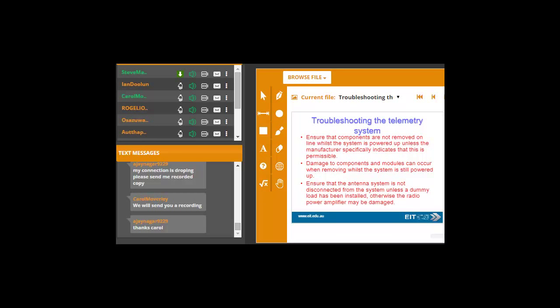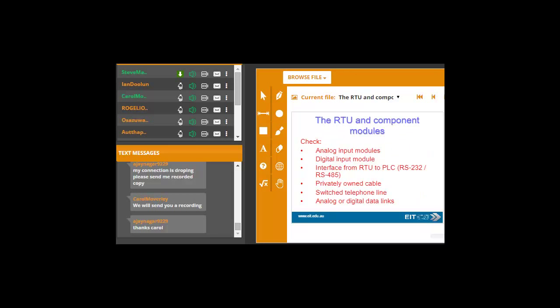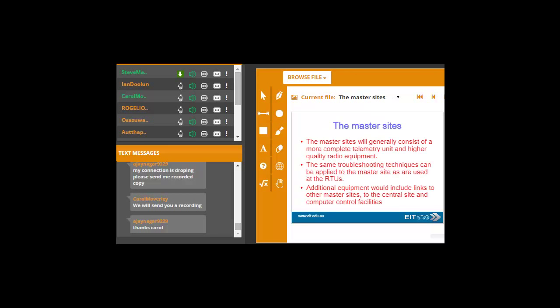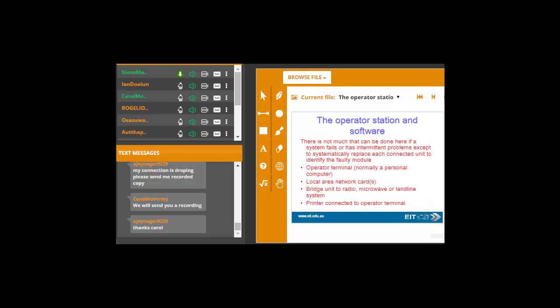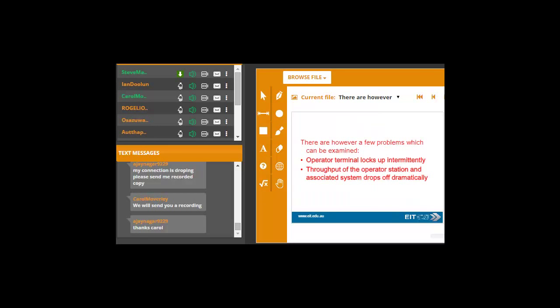So just to talk about troubleshooting of these links, just make sure the components are not removed while the system is powered up. And when you're removing components under load, you could cause a few issues. And obviously, just as far as the radio system is concerned, make sure the antenna system is not disconnected unless dummy load has been installed. Otherwise, you may damage your radio power amplifier. There's a few little issues on the side. The operator station really, as I said, the critical thing is if you see, for example, a few problems such as operator terminal locks up intermittently, you may find it's due to some electrical interference or spike that's come through the system. Or if your throughput drops off dramatically, you may find also that it's due to noise or interference on your communication link, which is causing multiple retries of your protocol messages.